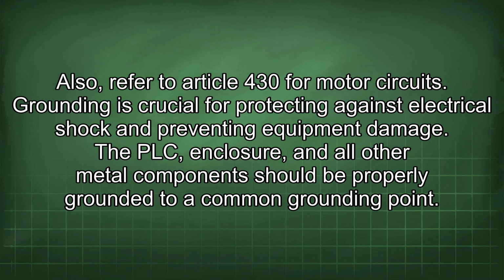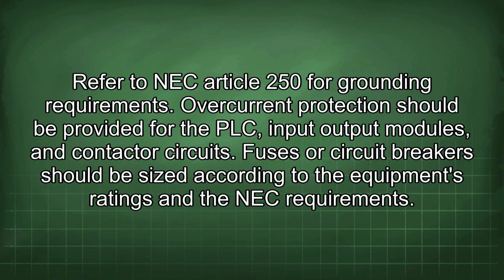Grounding is crucial for protecting against electrical shock and preventing equipment damage. The PLC, enclosure, and all other metal components should be properly grounded to a common grounding point. Refer to NEC Article 250 for grounding requirements. Overcurrent protection should be provided for the PLC input-output modules and contactor circuits. Fuses or circuit breakers should be sized according to the equipment's ratings and the NEC requirements.